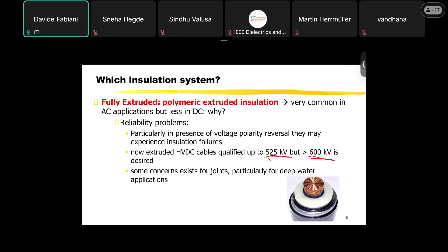But nowadays we have extruded polymeric HVDC cables that are qualified up to 525 kilovolt. So we have developed electrical insulation that is reliable also at high voltages. But the problem is that now we want to exceed 600 kilovolt. So the reliability concern about polymeric insulation is still present. In particular, in joints for deep water application, the use of polymeric fully extruded insulation is still not so common due to some reliability problems.